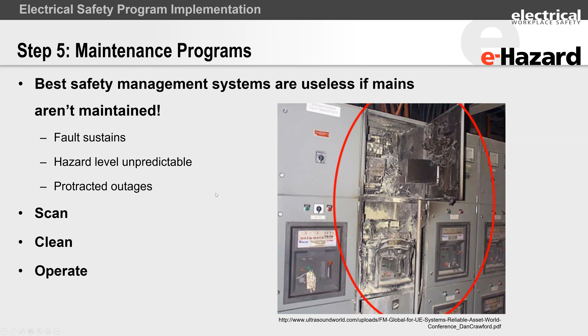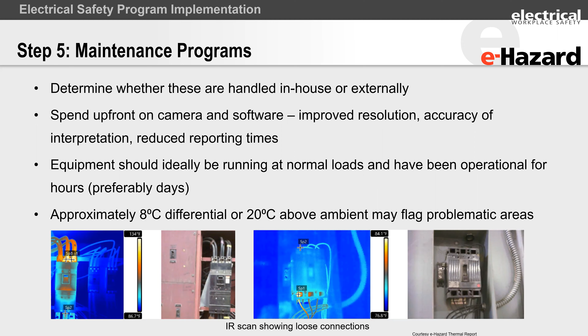One of the most basic and rudimentary forms of maintenance is a thermal scan. Even if you don't do anything else at the moment, just start off with a thermal scan. It can identify existing problems as well as developing problems at low voltage. Once you get into high voltage, there's a whole lot more you can do, but for low voltage, the very basic is infrared thermography, or an infrared scan as it's called. I've also put out a slide discussing what you can do with transformers, circuit breakers, panel boards, and some general requirements. Have a read through that in your own time.